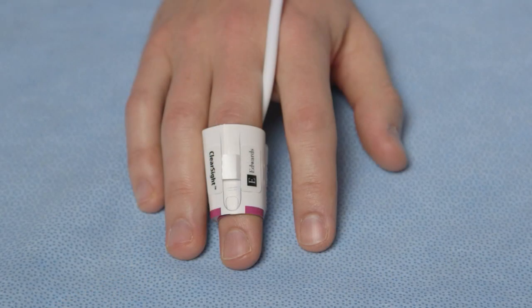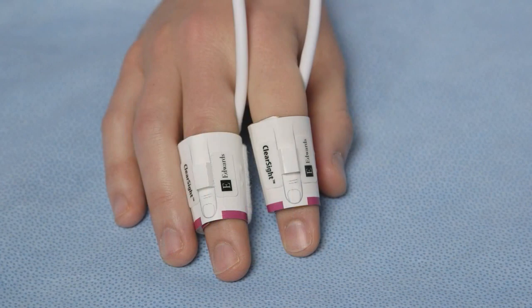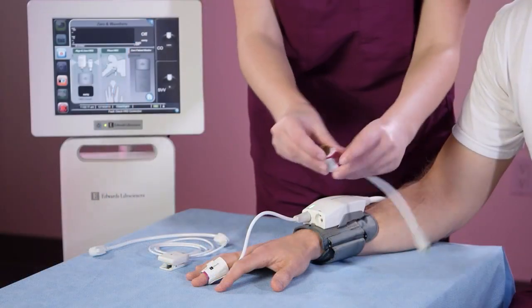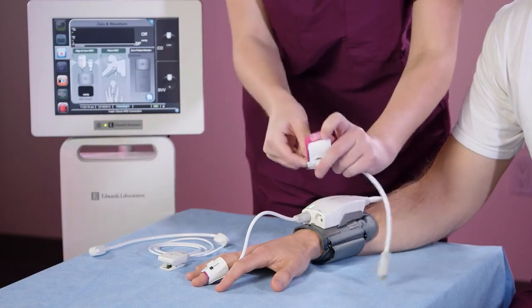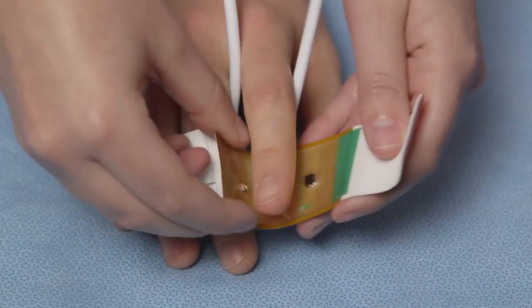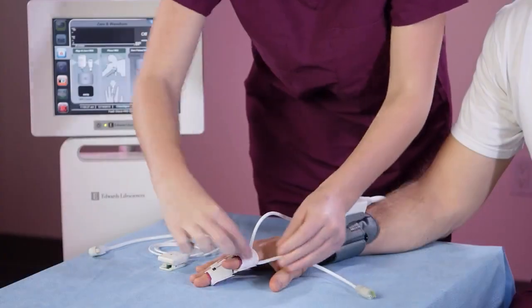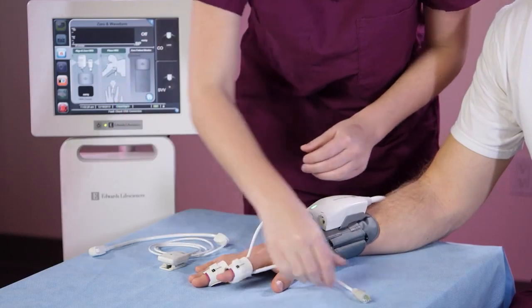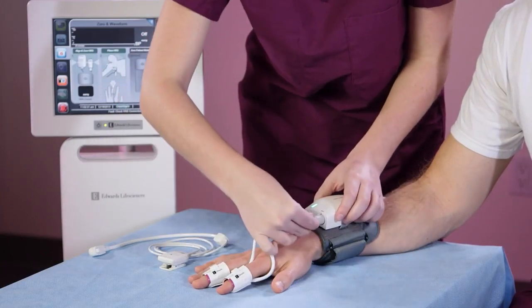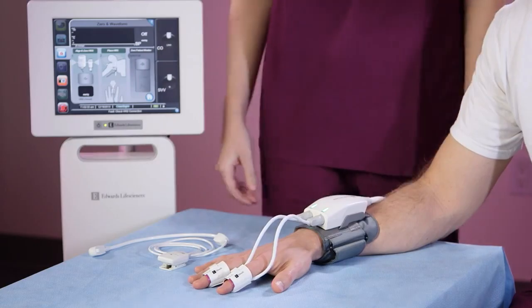One cuff will monitor continuously for 8 hours, after which the cuff must be moved to a different finger before monitoring can resume. Alternatively, the system can use two cuffs and alternate between the two every hour for 72 hours. If using two cuffs, repeat these steps on an adjacent finger with cuff number 2. Note that some fingertip discoloration due to venous congestion is expected when using the ClearSight finger cuff. This is not damaging to the patient.